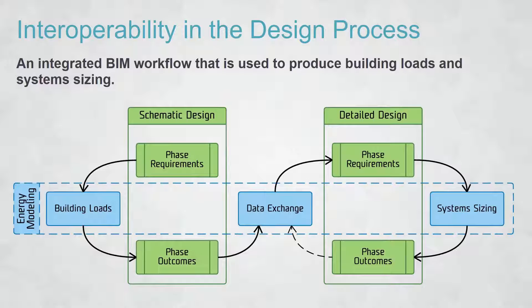What I've typically seen in the industry is that the initial model is done to produce your building loads, then you size your system accordingly. But the building ends up changing over this two- to three-month process, and the building loads never get updated — your systems are still being sized to these out-of-date loads. At the end, you're asked to create a LEED compliance report or ASHRAE 90.1 model, and the model just gets rebuilt, giving you two unrelated models — one simple at the beginning, one detailed at the end.